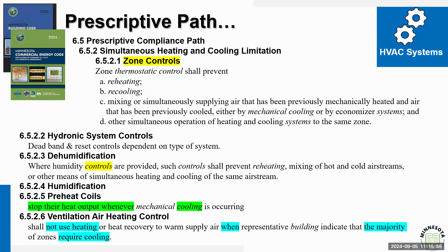If it's equipped with it, when the air temp - if we read this example here - the units are equipped with an economizer control so that when the outdoor air is at a temperature and humidity to provide free cooling, the damper will open to 100% to allow outdoor air to cool the space instead of the mechanical cooling equipment. It'll be equipped with a barometric relief to prevent the space from being overpressurized. That's the kind of awareness we want in the building.